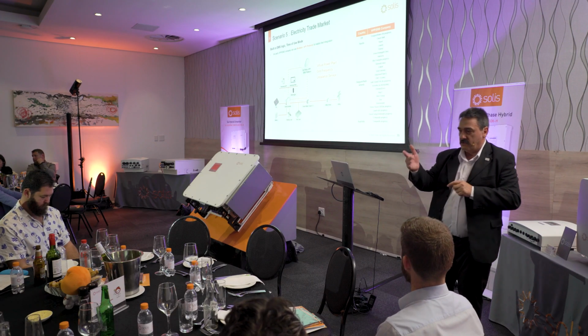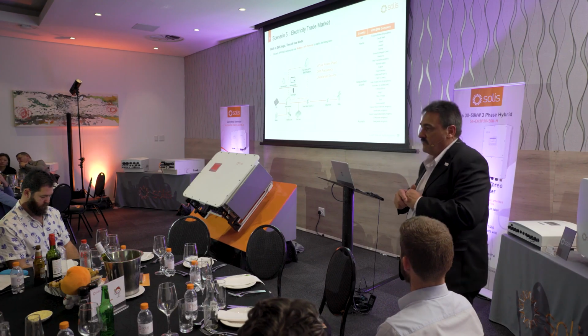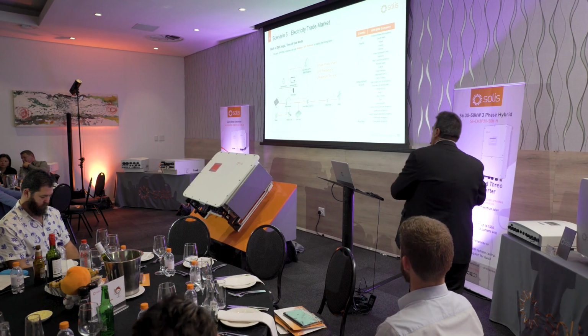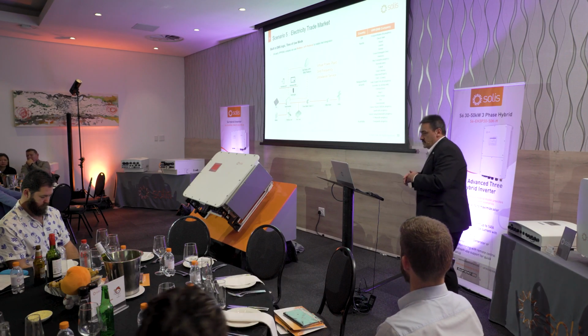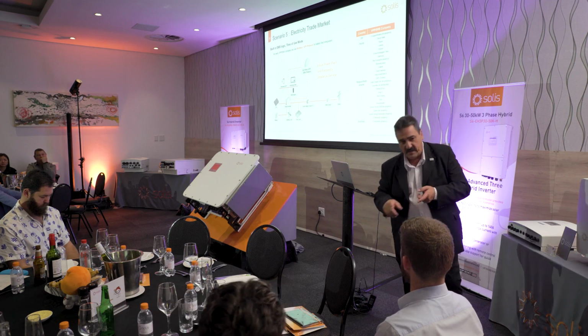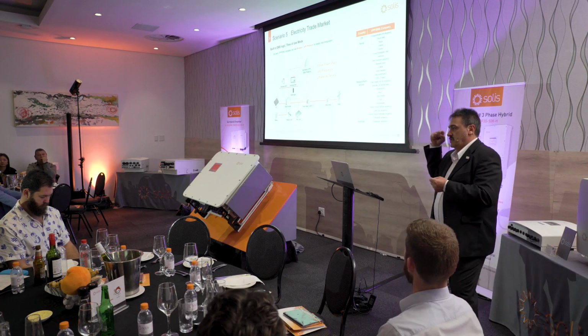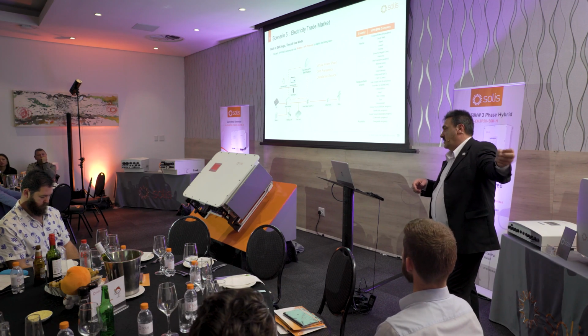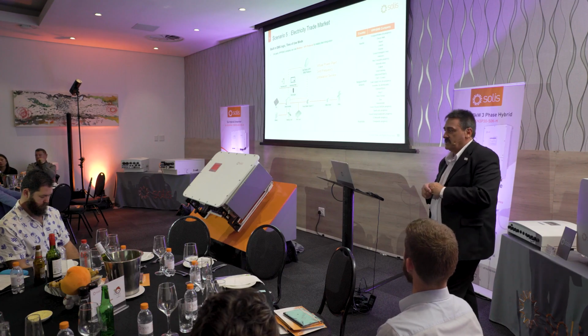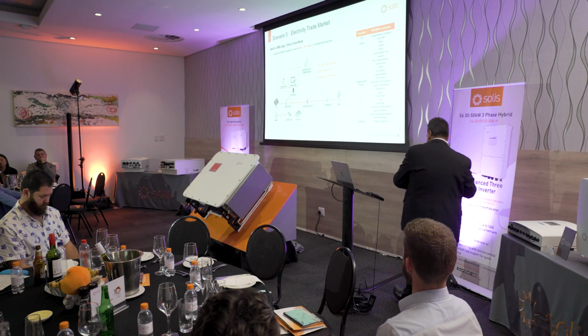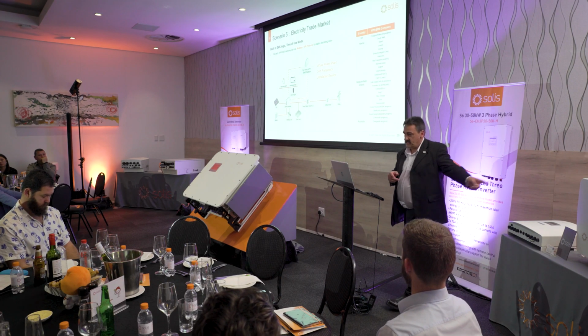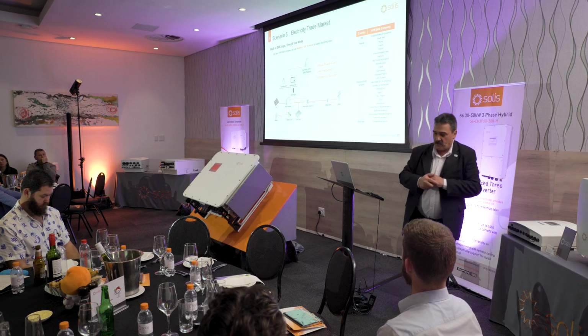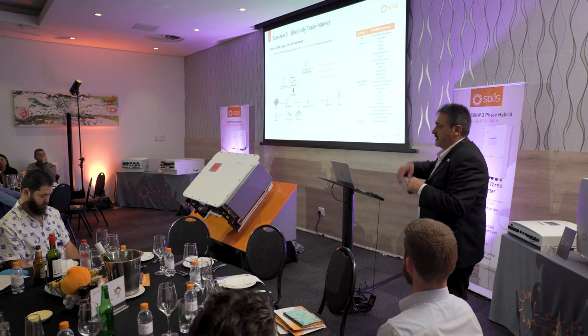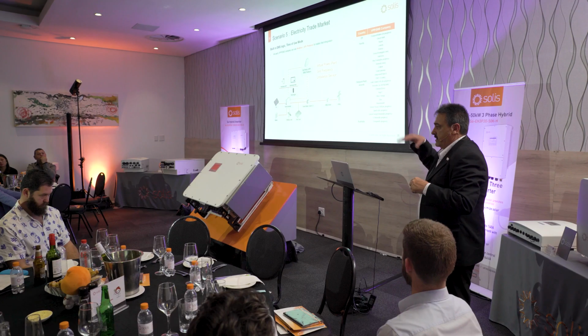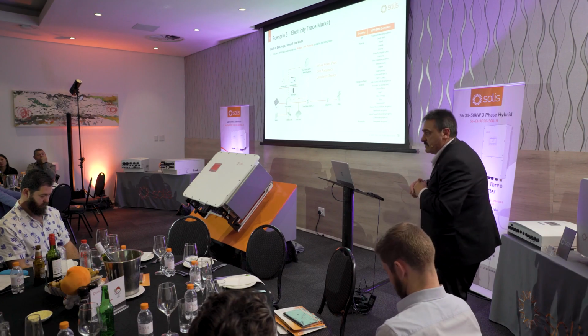In Cape Town, I think you've got the DNP3 protocol for everything over 100 kilowatts, right? The reason they want to use it all is to combat grid instability, they want to have control over that inverter. In the UK, they call it DRM, demand response management. Most of these devices have got a little port, a DRM port, that will control the inverter power from the council. It's like thinking back in the older days, the old ripple relays for the geyser, same thing.